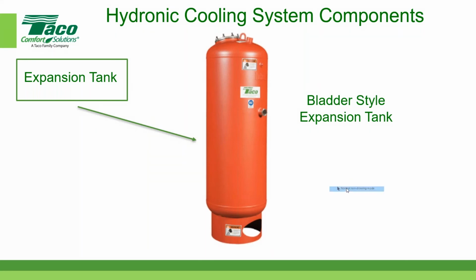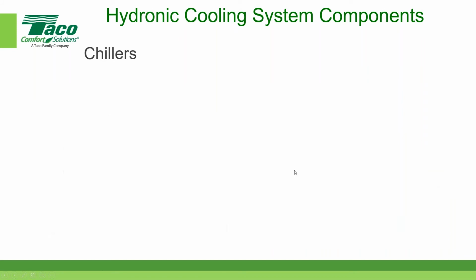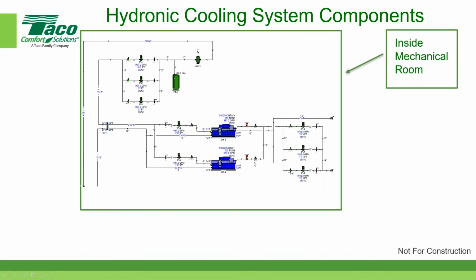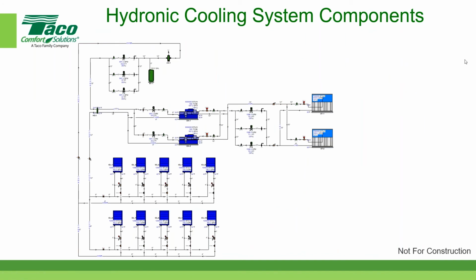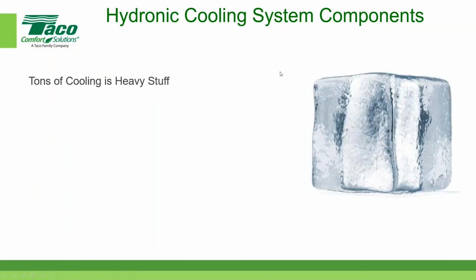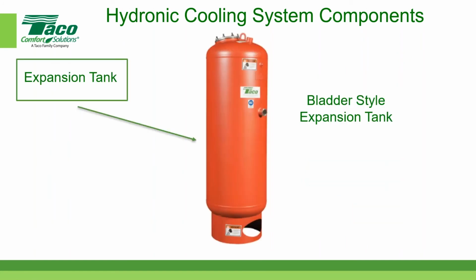Let's go back here to our system diagram. There's our complete system diagram, and the expansion tank is right here on this little diagram, and it's connected to the suction side of the pumps. There's the connection to the suction side of the pumps. And where it's connected right there is called the point of no pressure change. So the expansion tank is responsible not only for maintaining, let me get back to where we left off, the minimum pressure in concert with the fill valve, the maximum pressure, the expanding fluid, and also the point of no pressure change.